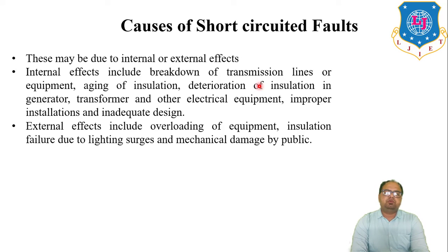Now, what are the causes of short circuit faults? These may be due to internal or external effects. Internal effects include breakdown of transmission lines or equipment, aging of insulation, deterioration of insulation in generators, transformers and other electrical equipment, improper installation and inadequate design. External effects include overloading of the equipment, insulation failure due to lightning surge, and mechanical damage by the public.